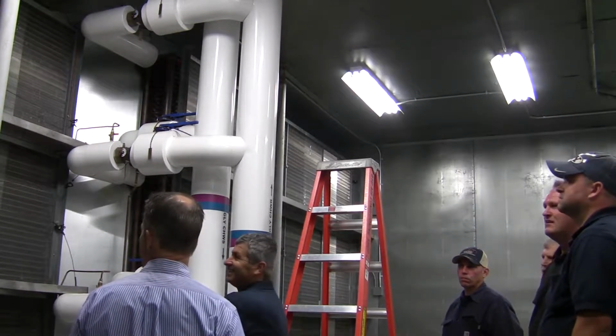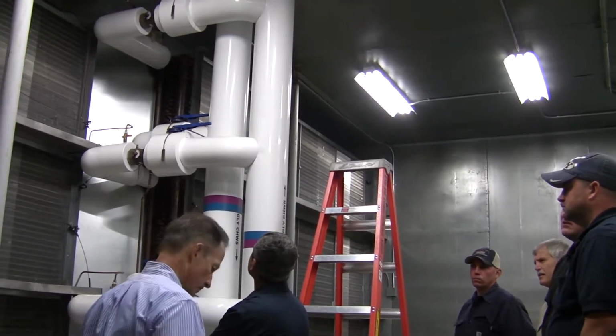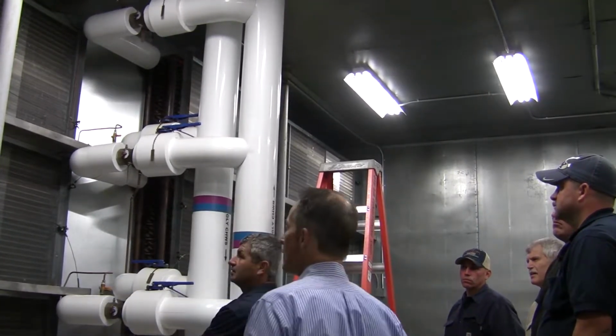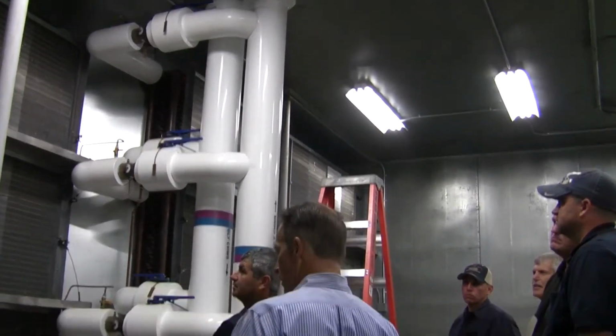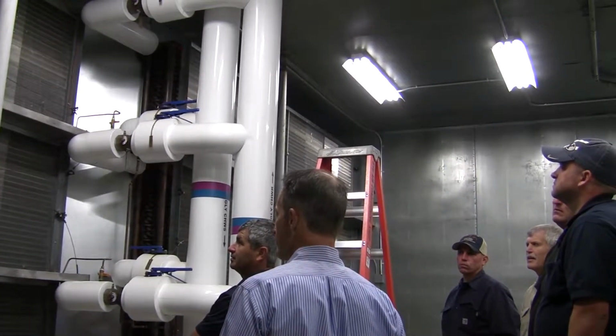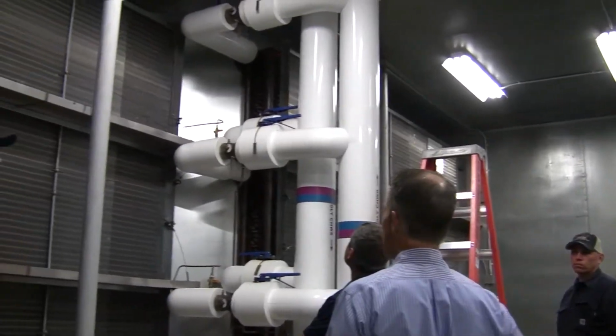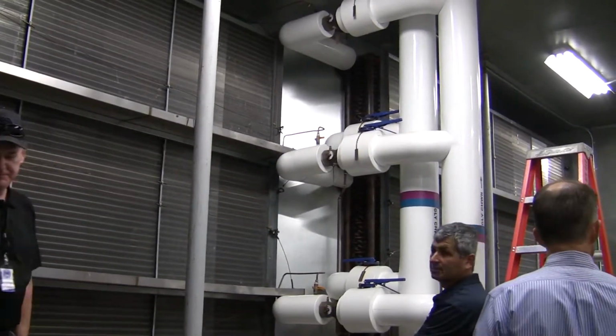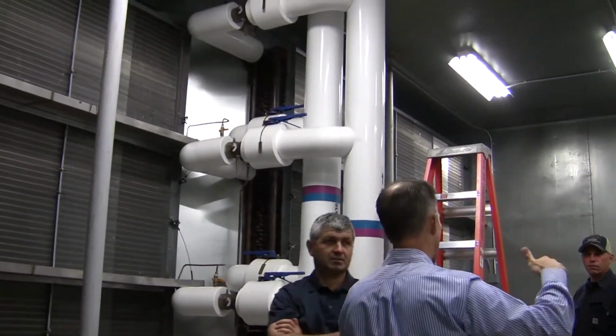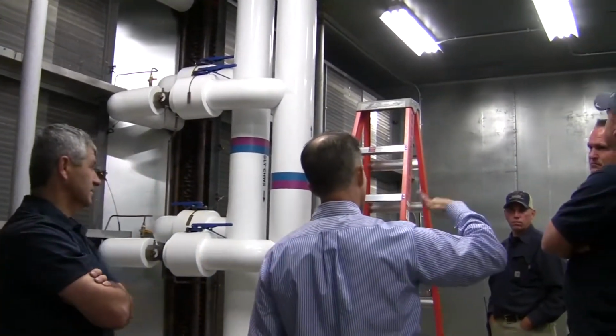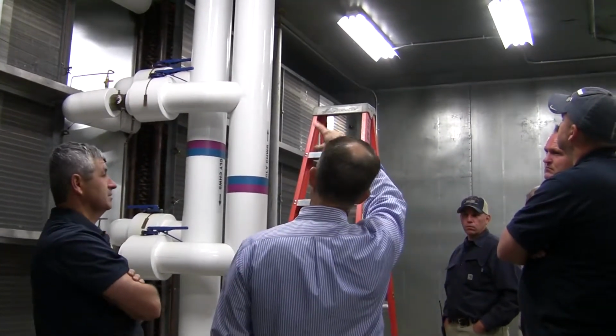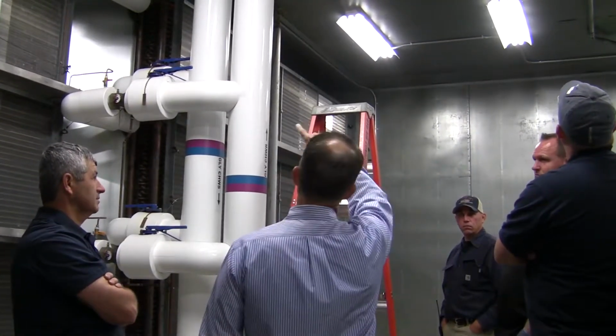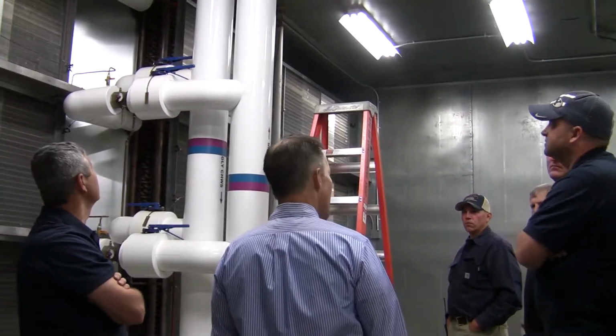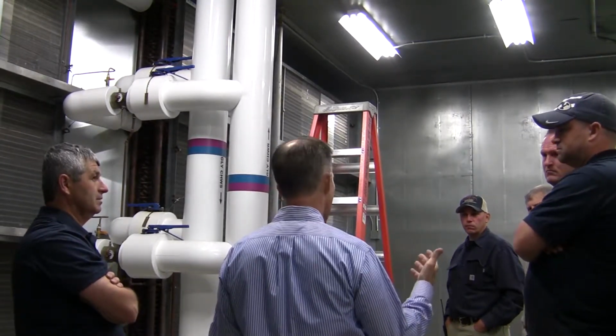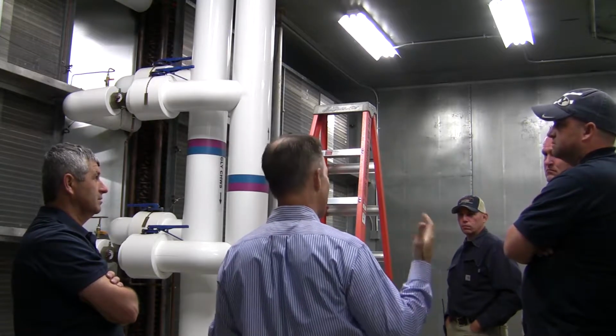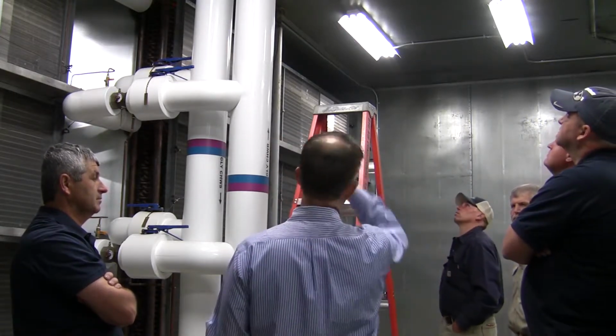Yeah, there's an air handler, I think it was in the Tanner building. Everything was good, but get on a ladder, there was a strip 3 to 4 inches across the top of the coils that wasn't sealed. It was just leaking air over the top. So when these fans are running, right now we've got them down to 35%, normally they run about 55%. You'll probably get anywhere from 200 to 300 CFM that'll leak through that, being pulled through. I ran a quick calculation, it was about $250 to $300 a year in energy waste from that air coming through there.